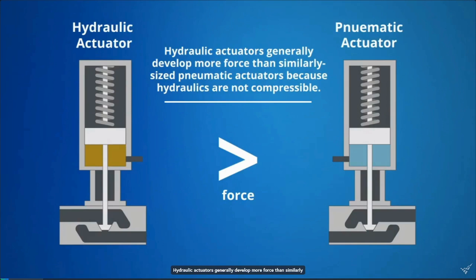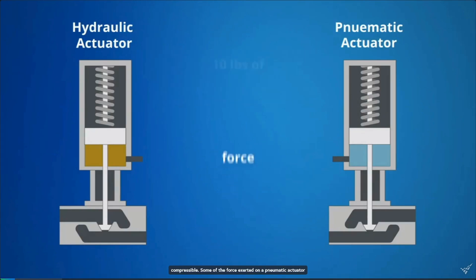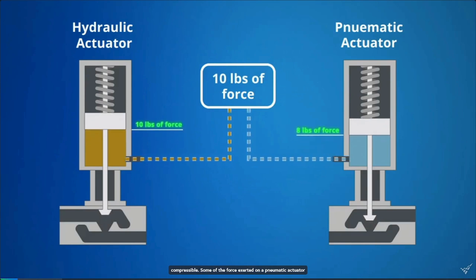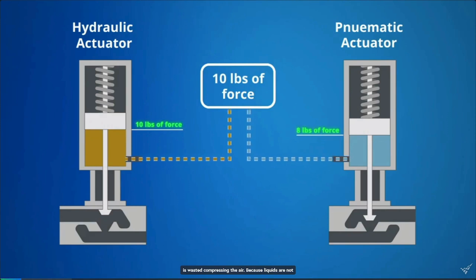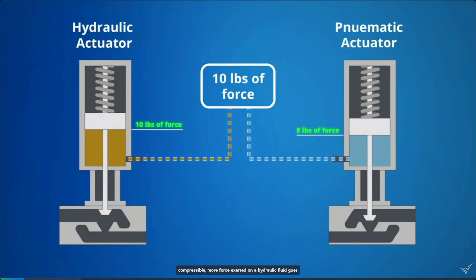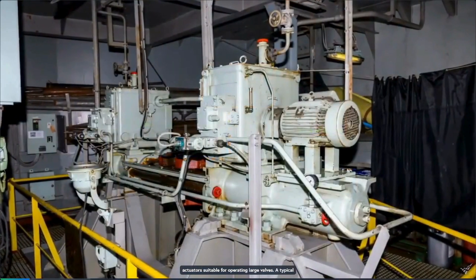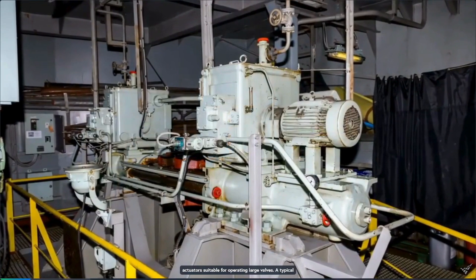Hydraulic actuators generally develop more force than similarly sized pneumatic actuators because hydraulics are not compressible. Some of the force exerted on a pneumatic actuator is wasted compressing the air. Because liquids are not compressible, more force exerted on a hydraulic fluid goes directly to positioning the valve. This makes hydraulic actuators suitable for operating large valves.